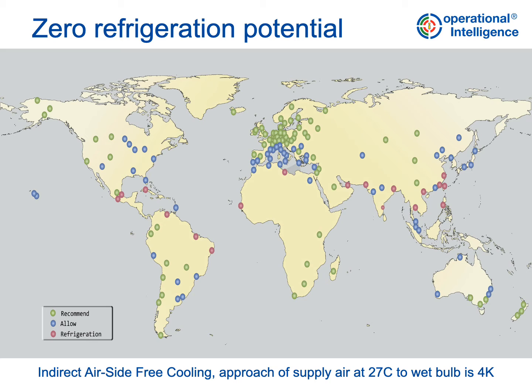This image shows the results of a study we've undertaken to analyse free cooling potential in different climates. The assumption is an optimised cooling design based on indirect airside free cooling, which uses adiabatic evaporative cooling rather than compressor-based cooling. The locations with a green dot can use this technology and supply air within the recommended range, up to 27 degrees C. Those with a blue dot would have temperatures within the allowable A1 range, which is up to 32 degrees. Locations with a tropical climate, shown in red, would require refrigeration in this kind of system.